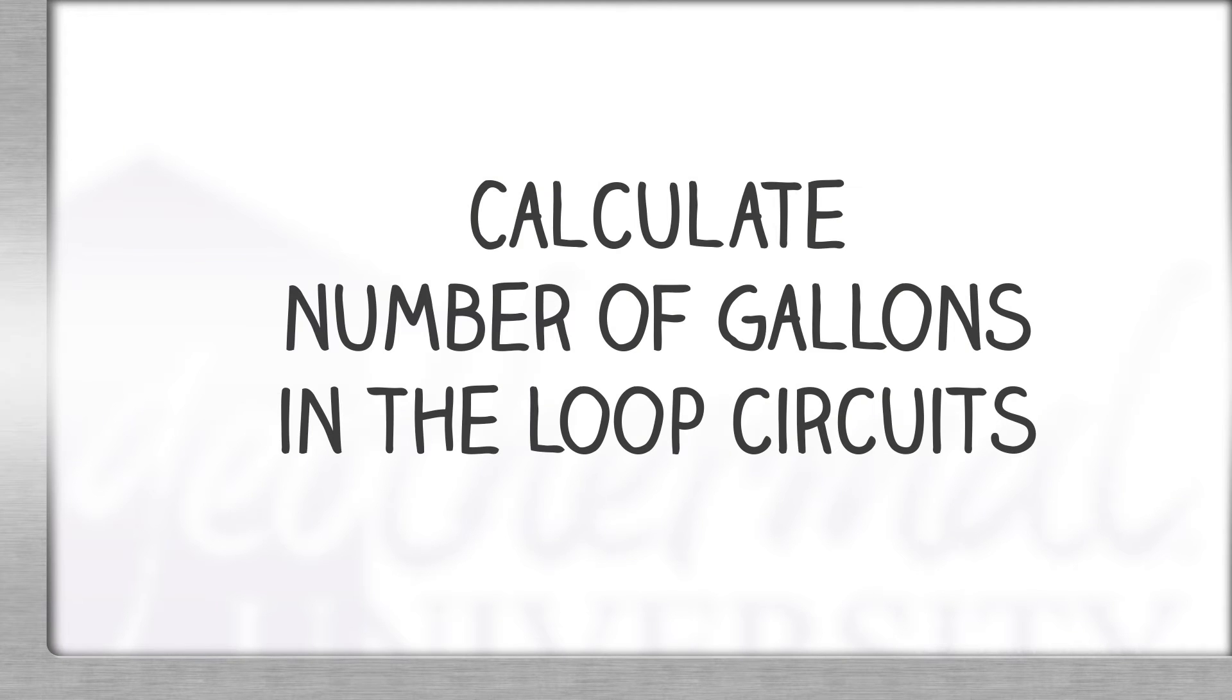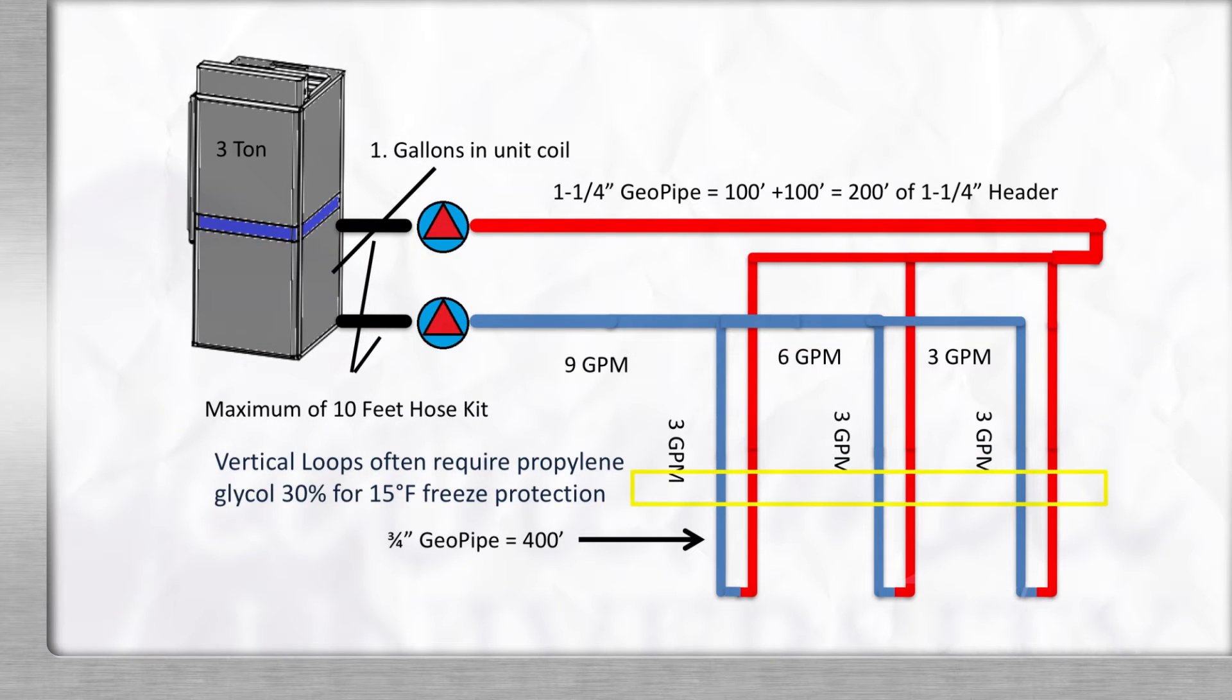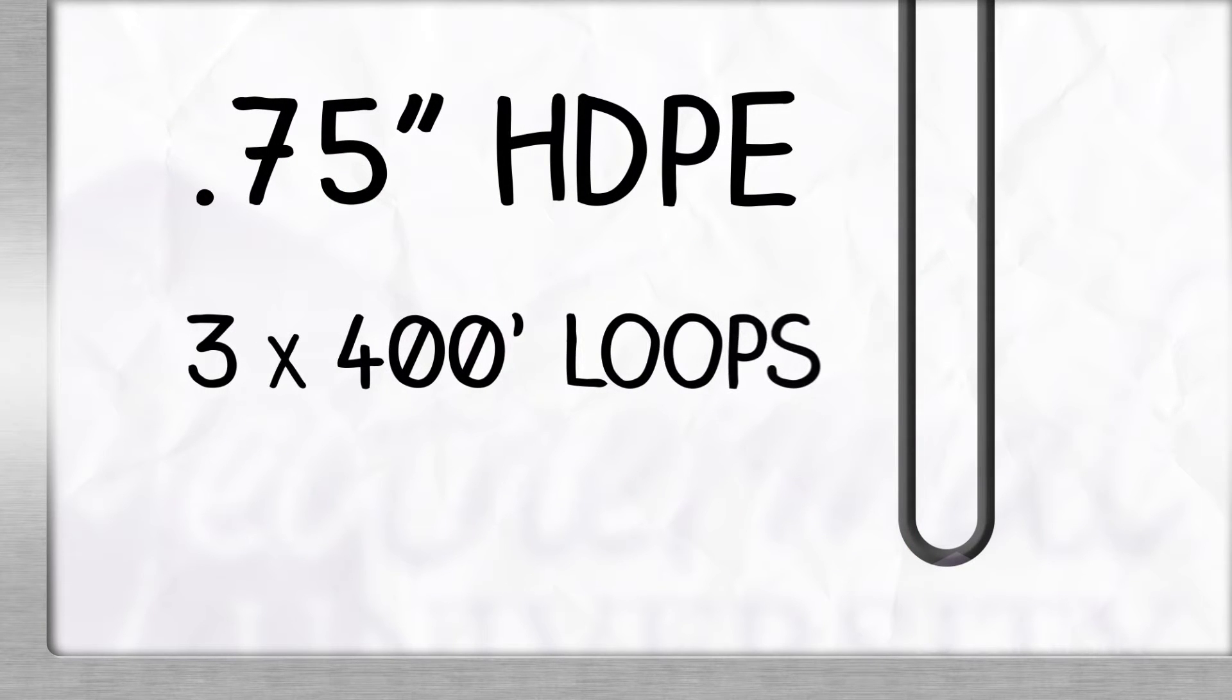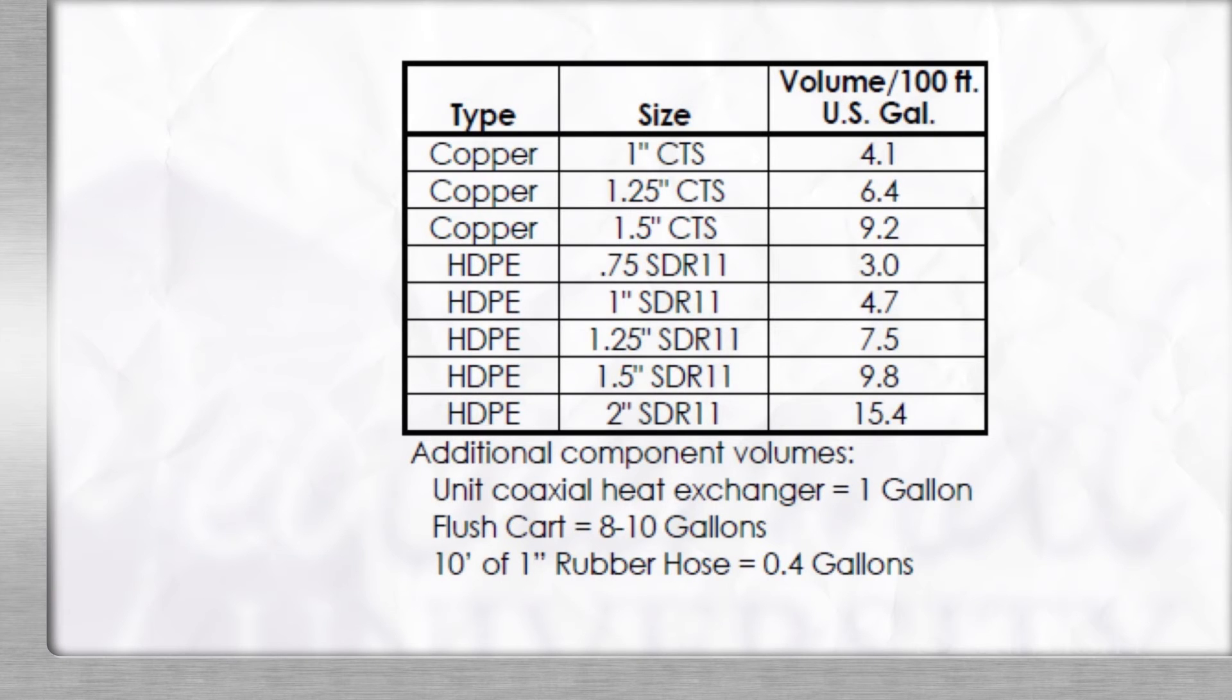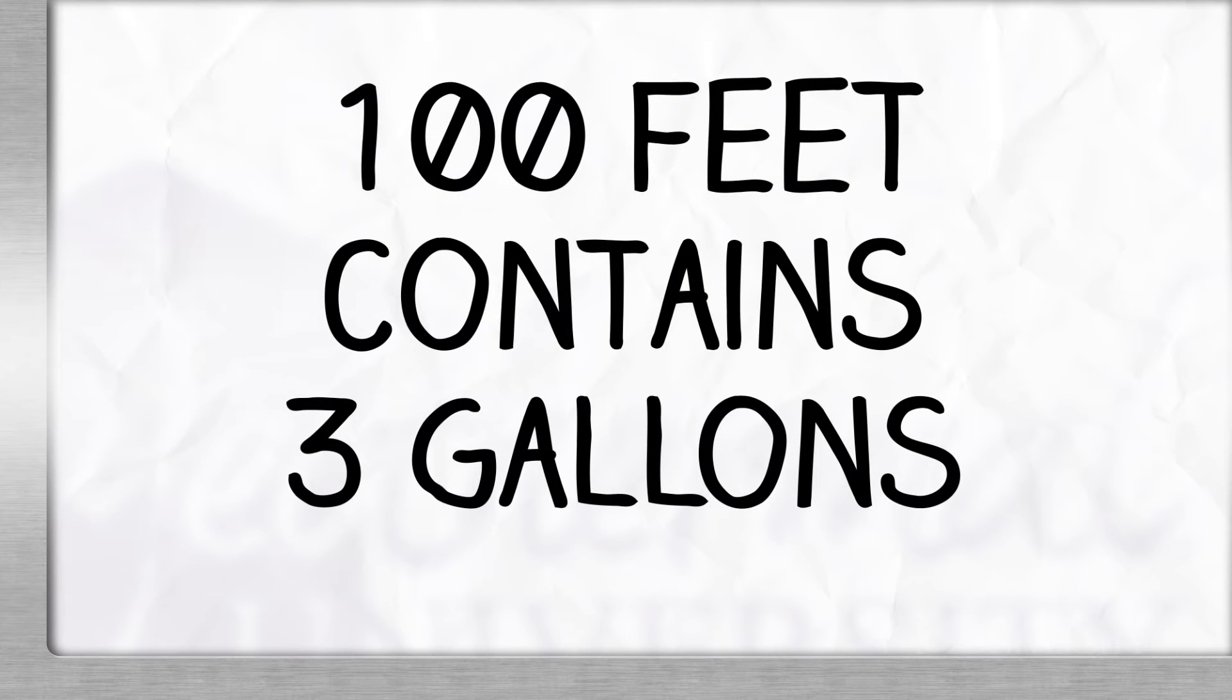Next, we'll need to calculate the number of gallons in all the loop circuits. In our example, our loop circuits consist of three-quarter inch HDPE pipe and three 400-foot loops. That is 200 down and 200 up. Using the table provided in the IOM, we scroll down to three-quarter inch SDR 11, and we find 100 feet contains 3 gallons.